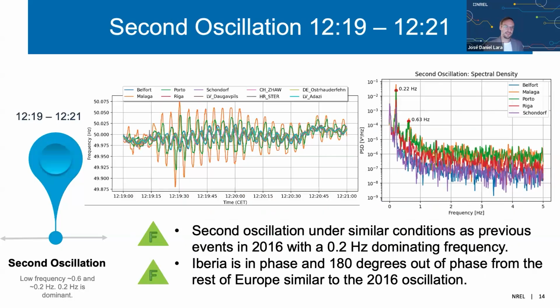The second oscillation happens a few minutes later, and this oscillation has a significantly different signature. Here we can see that it's actually against the rest of the European system, with a signature of around 0.22 hertz. Now we can observe the rest of the European system oscillating, not only locally for Malaga and Porto, but also against other nodes as far away as Latvia, Switzerland, Germany, and France.